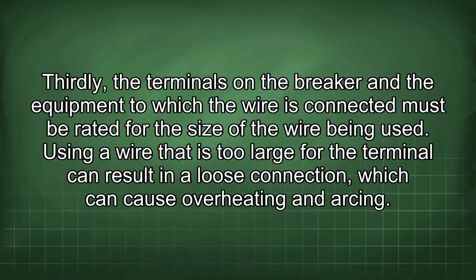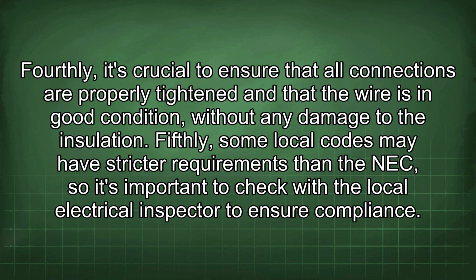Thirdly, the terminals on the breaker and the equipment to which the wire is connected must be rated for the size of the wire being used. Using a wire that is too large for the terminal can result in a loose connection, which can cause overheating and arcing. Fourthly, it's crucial to ensure that all connections are properly tightened and that the wire is in good condition without any damage to the insulation.